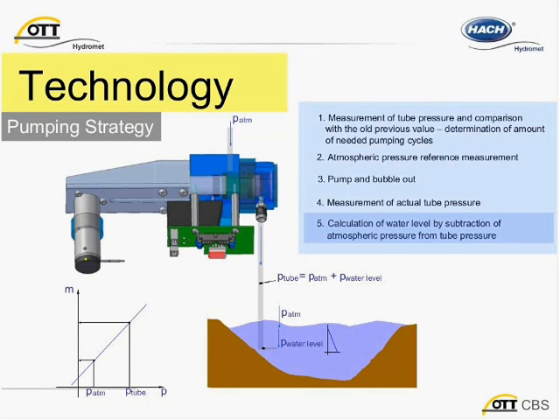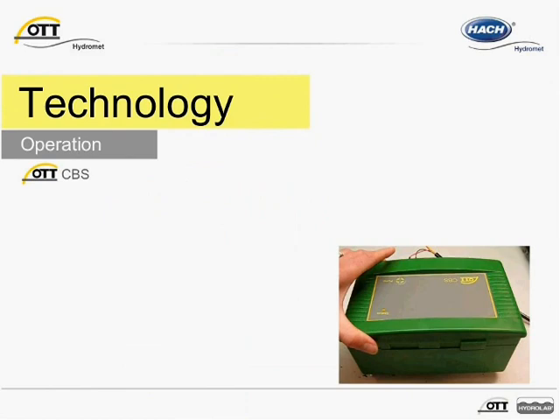The water level measurement is calculated by subtracting atmospheric pressure from the tube pressure. Now let's take a detailed look at the compact bubble sensor. The internal piston pump generates compressed air, which is then pushed through the measuring tube and out of the bubble chamber for each and every measurement. That means the piston pump is inactive between measurements.